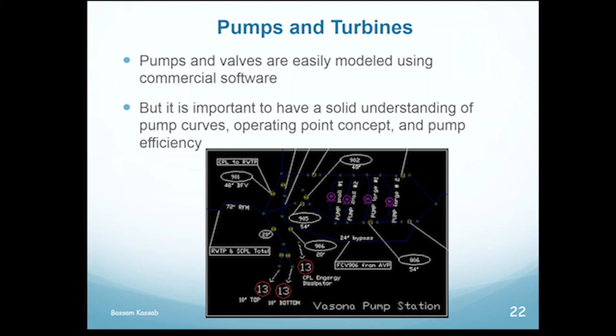And pump curves, I know many engineers and operators ask me about pump curves. They're a little bit confusing. That's why I want to dedicate a couple of slides to talk about pump curves here and share my understanding of pumps with you. A pump characteristic curve, what I'm showing you here with the mouse, is called the pump head curve or pump characteristic curve. It comes from the manufacturer. Basically, it's a plot of the head of the pump, the head that the pump generates, versus the flow.